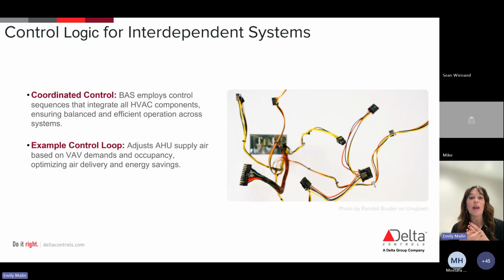And then that third component of your control loop is going to be an actuator, or something that is adjusting the system output to minimize the difference between the measured condition and the set point. So basically what we're trying to do is create the set point that we want in each of our zones, and we need to know how to get from point A to point B. Like Moose took us through, these loops can operate in both open loop and closed loop. Open is just going to be no feedback. Closed is going to be more feedback-driven configurations. Closed loop is going to be able to provide continuous adjustments for a little bit more precise regulation.